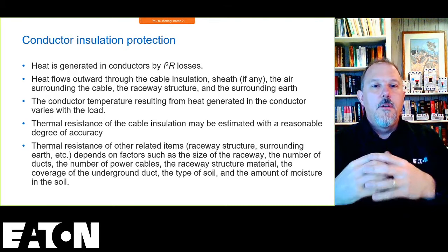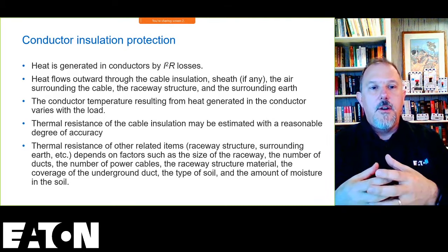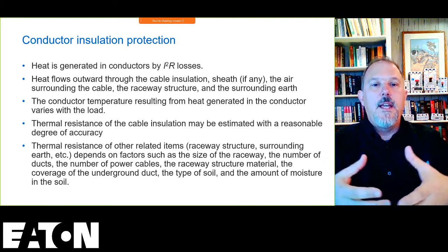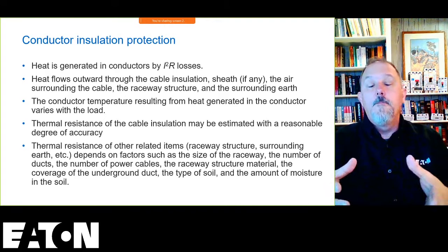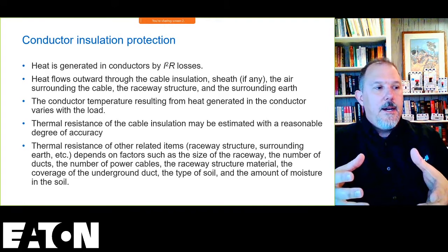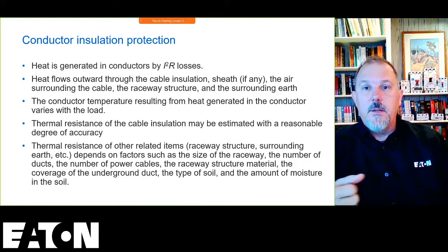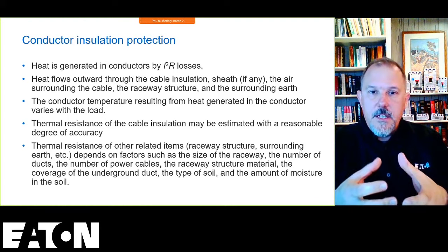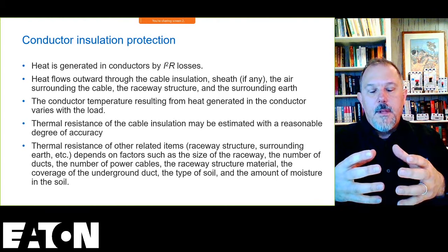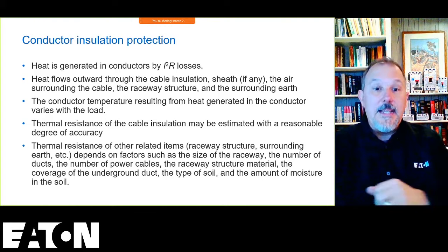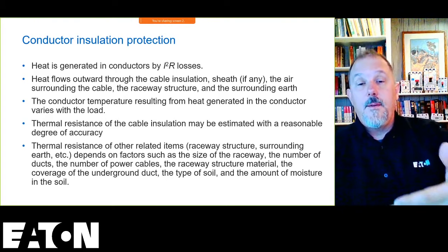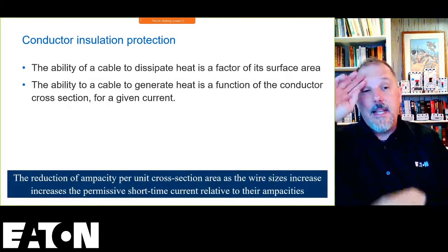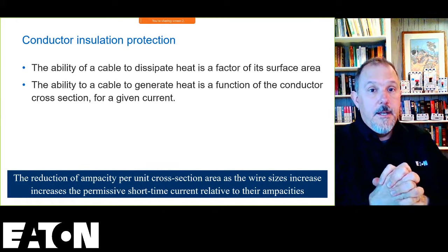So you're looking at the resistance of that conductor, current passing through the conductor, heating the conductor, and then it makes its way out through the system. So if I have a conductor in open air as opposed to maybe in a raceway of some sort, or if I have bundling of conductors, that limits the ability to dissipate that heat. And that is why we will have to impact the ampacity of that conductor. We have to take those under consideration.